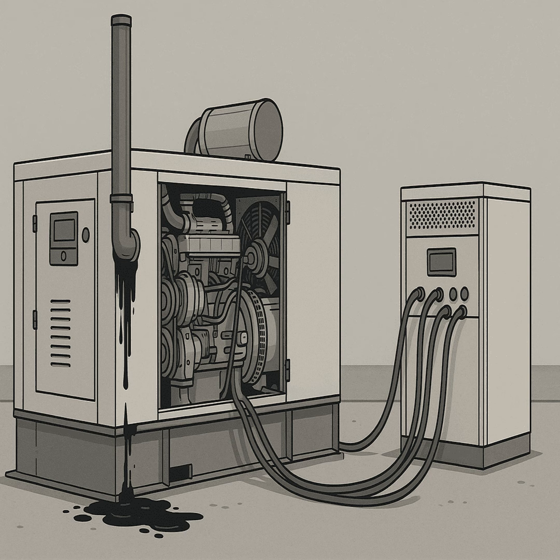It happens when a generator runs frequently with very little or sometimes even no electrical load connected to it. Or another common scenario is when the generator itself is just too big for the job it's doing. It's oversized for the actual demand. Right, so it never really has to work hard.